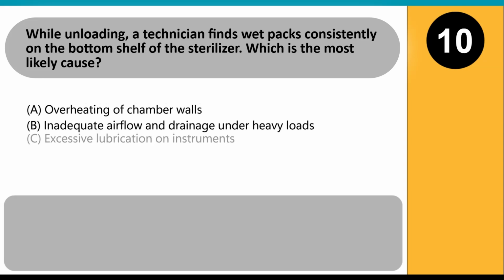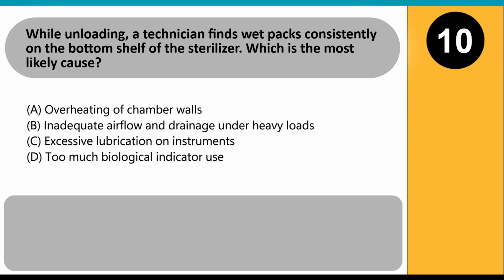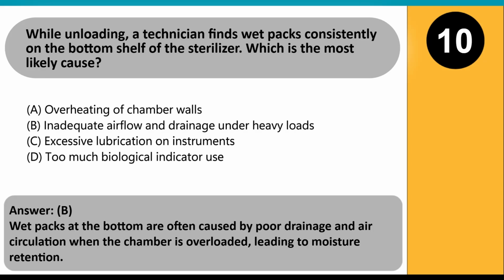While unloading, a technician finds wet packs consistently on the bottom shelf of the sterilizer. Which is the most likely cause? A. Overheating of chamber walls. B. Inadequate airflow and drainage under heavy loads. C. Excessive lubrication on instruments. D. Too much biological indicator use. Answer: B. Wet packs at the bottom are often caused by poor drainage and air circulation when the chamber is overloaded, leading to moisture retention.